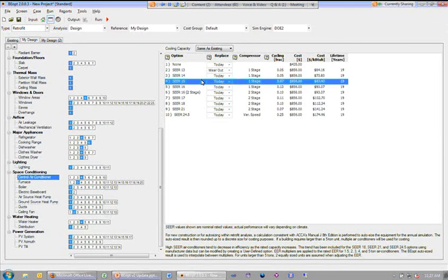So just to be clear here, this column of data that is labeled replace, this refers to the existing equipment, and the most conservative thing is assume that it gets replaced when it wears out, at which point if you upgrade it optionally to a higher SEER equipment than the minimum federal standard, at that point you had to buy a new air conditioner anyway, and so the cost associated with the energy efficiency is the incremental cost of the more efficient air conditioner.